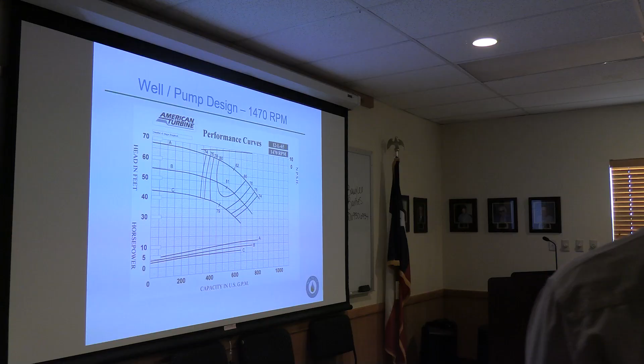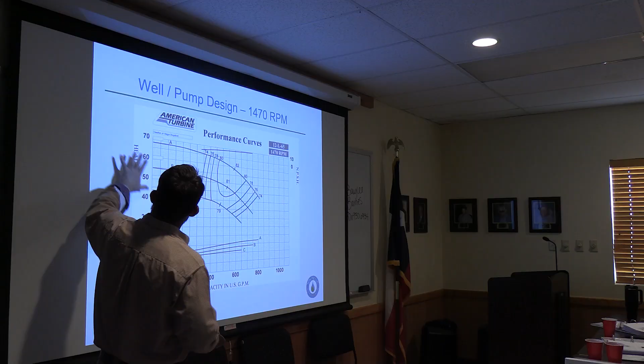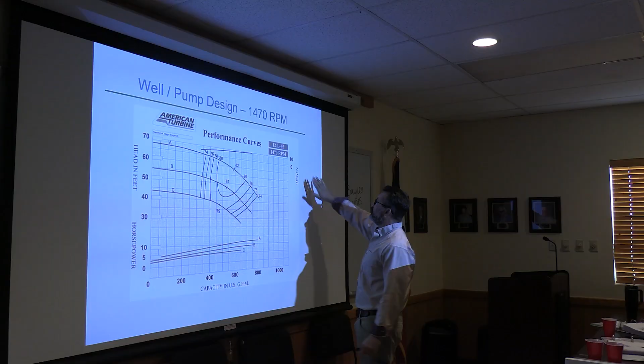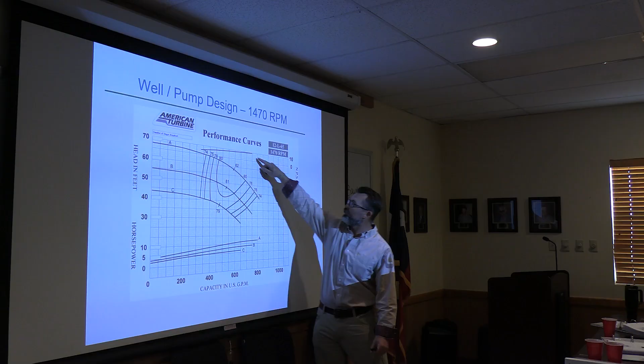So to get your orientation on this pump curve, you're looking at capacity in gallons, and then you'd have horsepower for this chart, and then you would have the head developed per stage on this chart, and then this number up here is referred to as your net positive suction head, which means how much water you need to have above the inlet of the pump. Okay, so 0 to 10. You can see that as the flow goes up, you need to have more feet above the pump. As the flow's down, you don't need so much, etc.